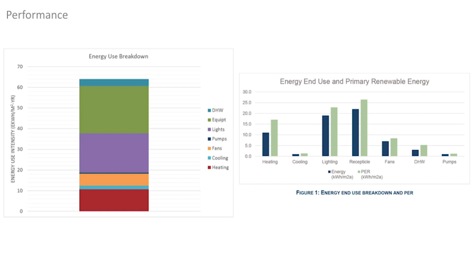This slide starts to show how, as designers, we control our base building loads, but lighting and plug loads become such a huge part of the puzzle, and that's something we don't have much control over. So we worked with Humber to look at a lot of their existing buildings to get more accurate information on how people actually use plug loads and process loads, because we tend to overprogram them. The problem is engineers start designing for a cooling load that doesn't exist. I know you can't read this well, but it's just a backdrop.